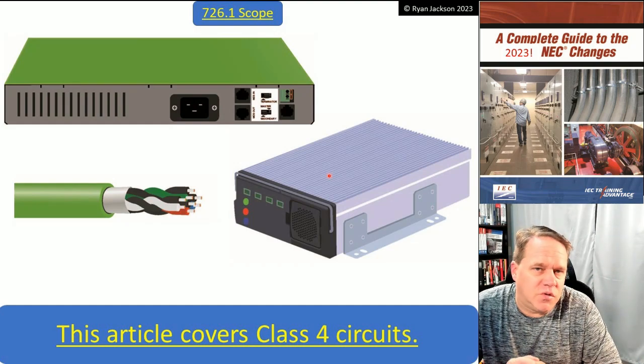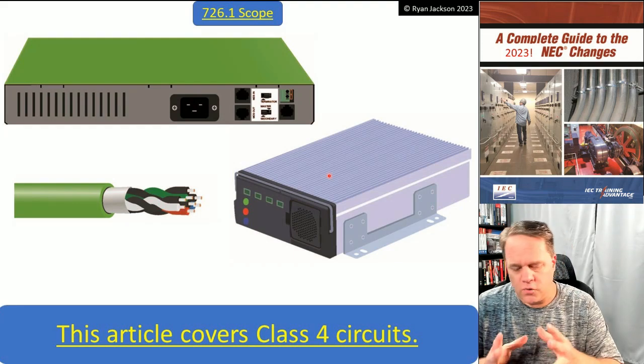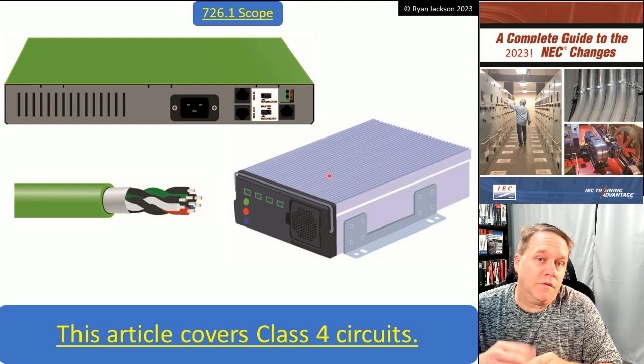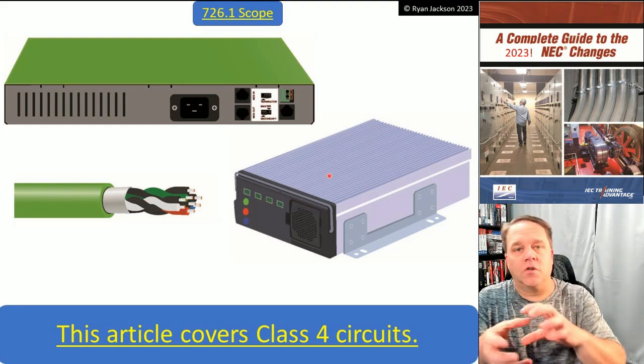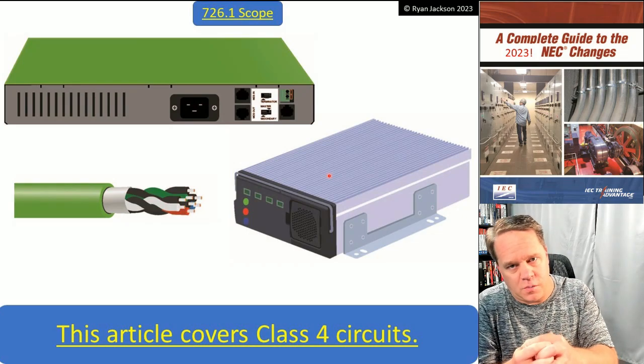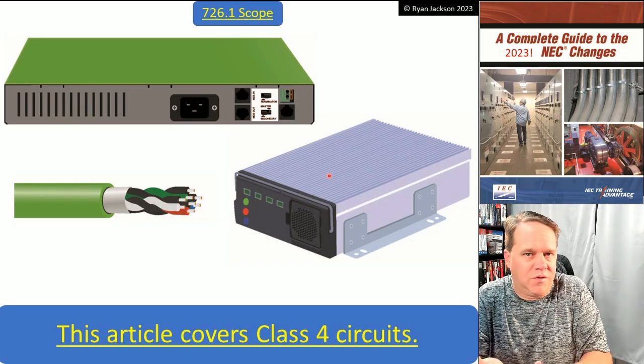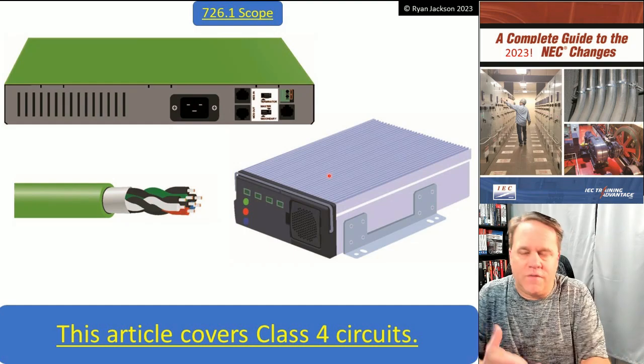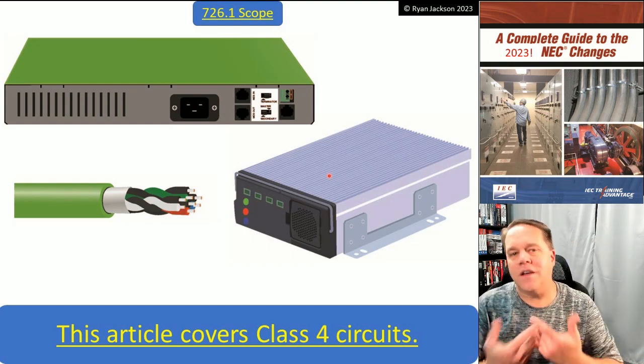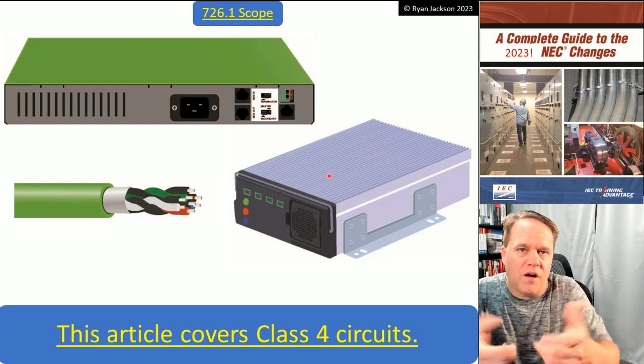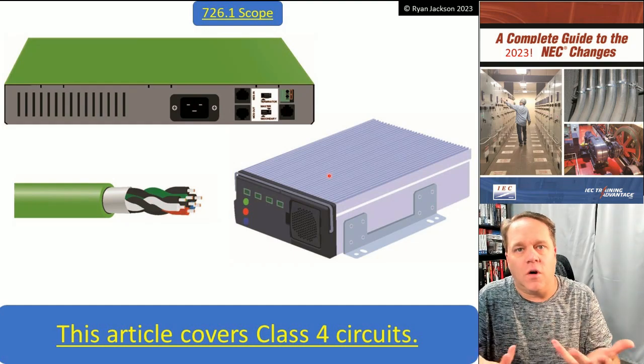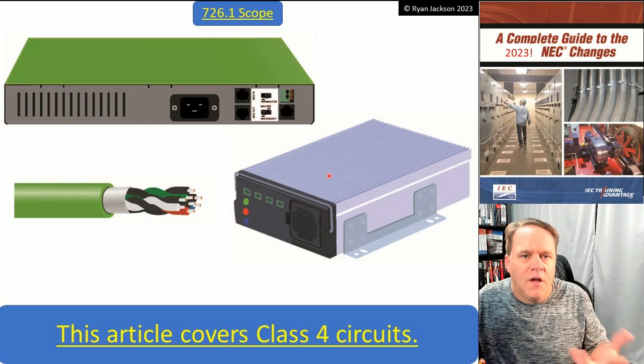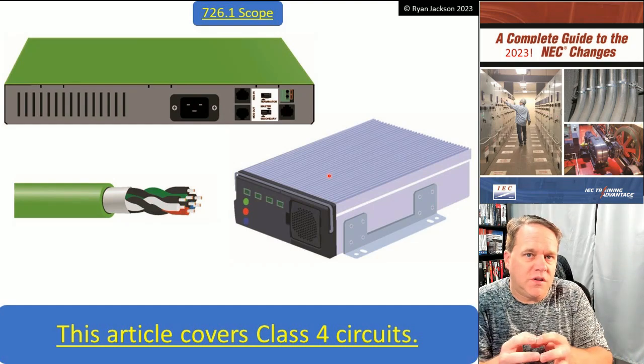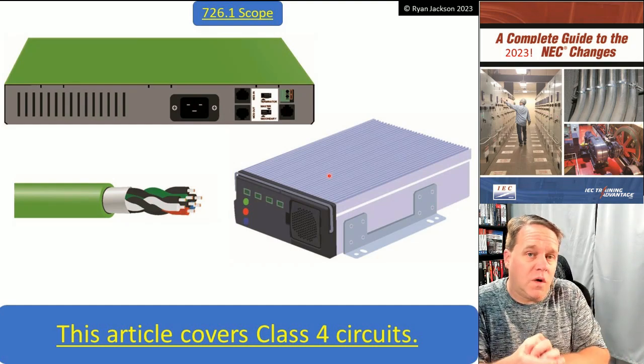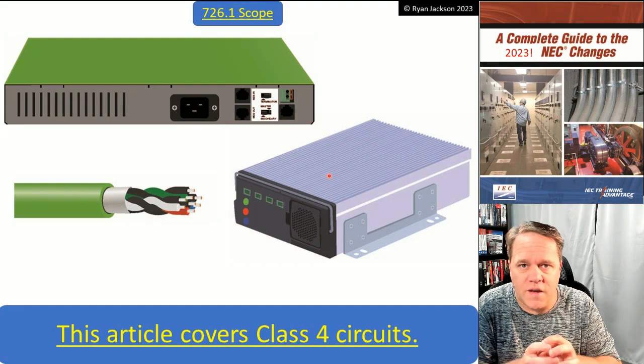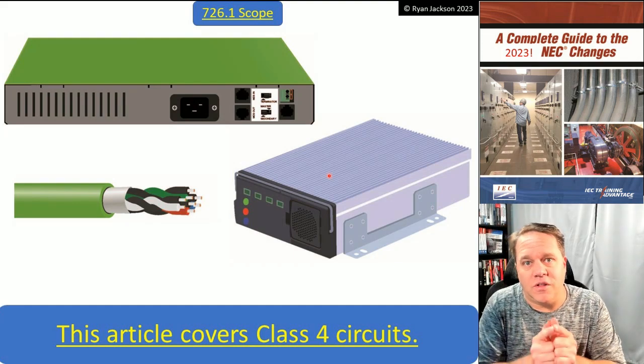Think of a Class 2 circuit, like a doorbell. The doorbell is limited in the amount of voltage and current that you can have on the circuit. It's limited by the power source, by the transformer. You can't kill anybody with a doorbell transformer. There's not enough voltage to drive enough current to stop the human heart. You can't light a fire with it. I mean, you bang the wires together, there's not enough I2R heating to create a fire. So the voltage and power limitations of the power source is what makes a Class 2 or a Class 3 circuit safe. That's not the case with Class 4.